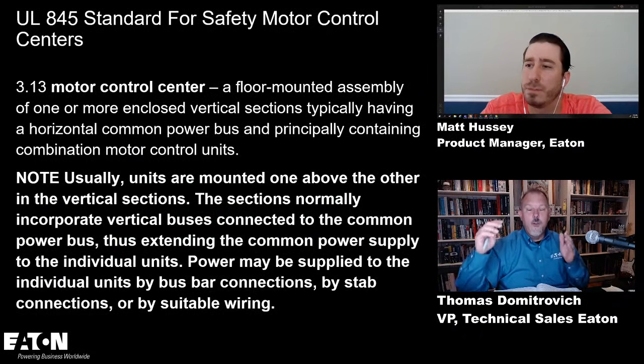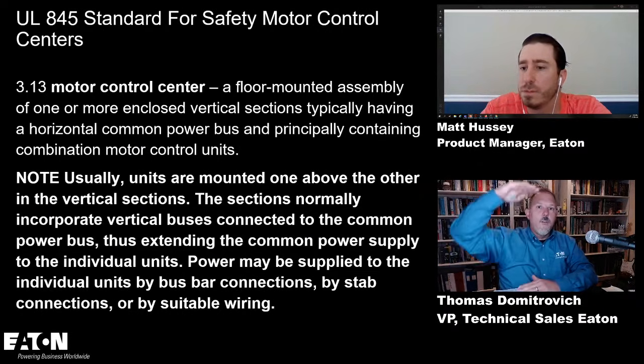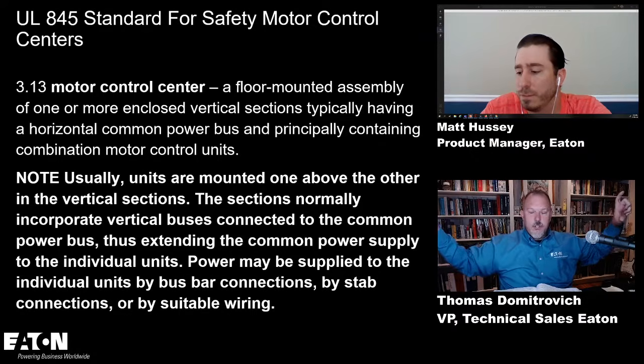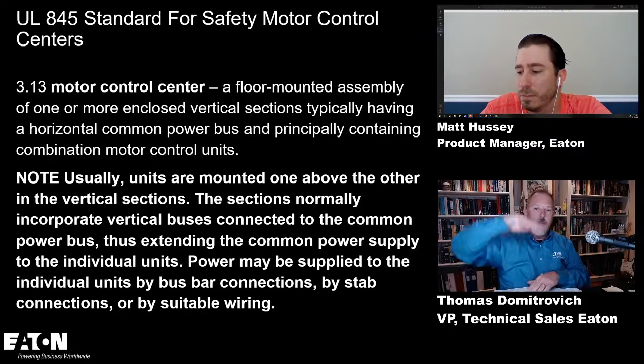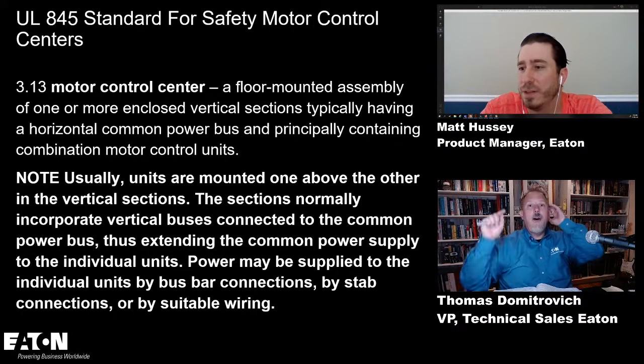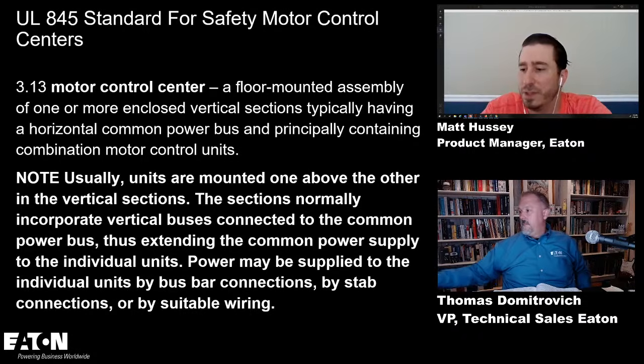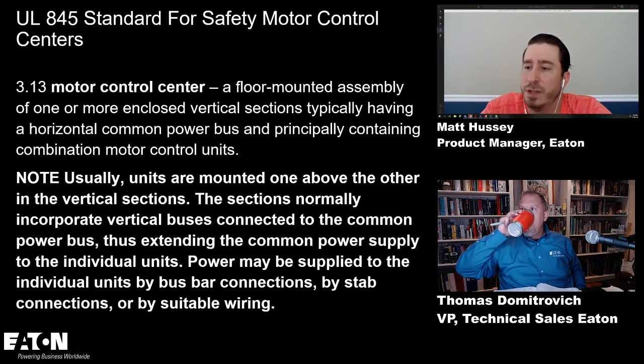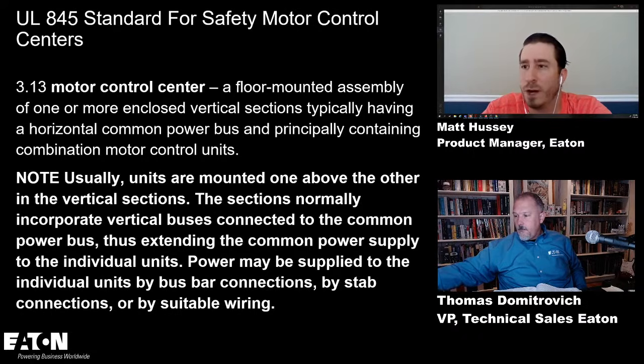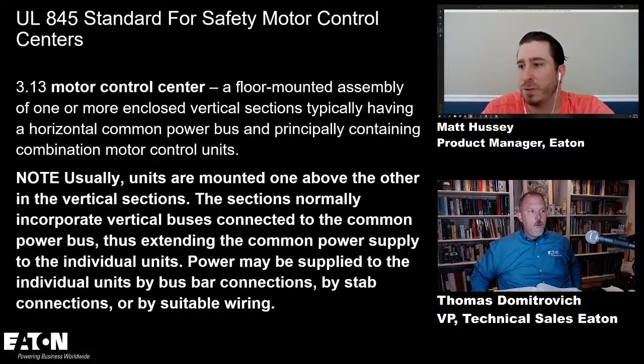So motor control center, floor mounted. My MCC buckets are one over top of each other. I don't make them horizontal. There's no such thing as a horizontal MCC, they go from the floor up, right? Yep, that's correct. How many units high? Typically, they're about 90 inches tall as a vertical section, and in each vertical section you're going to have wireway space. So that usually leaves about 70 or so inches to work with, depending on manufacturer. Usually that gets subdivided into compartment heights of maybe 6 inches to 12 inches tall. So you get about 6 to 12 units per vertical section.